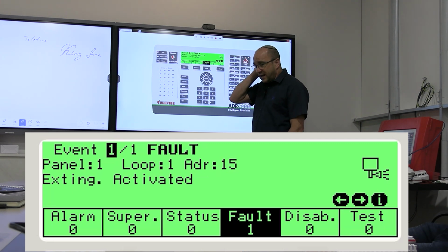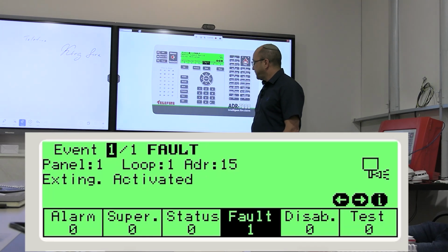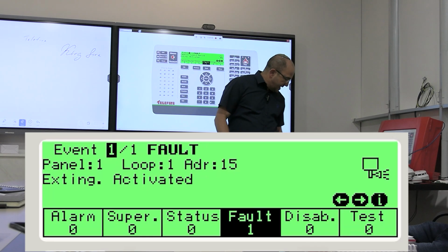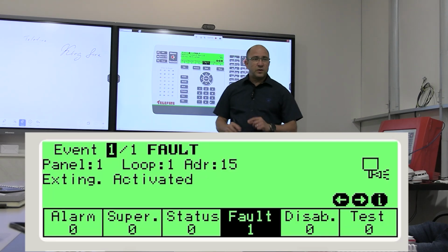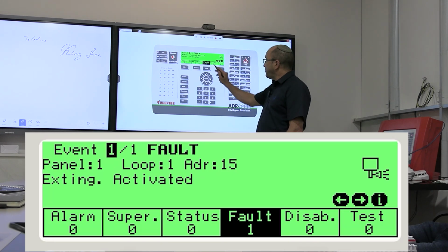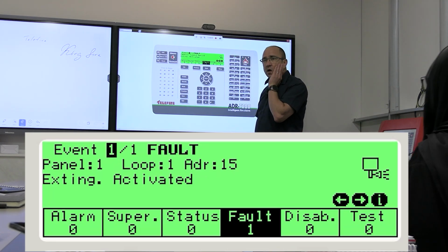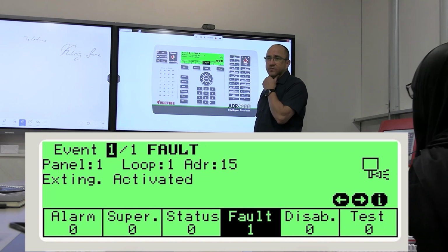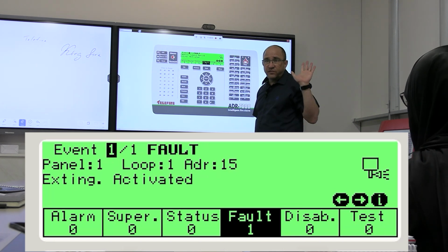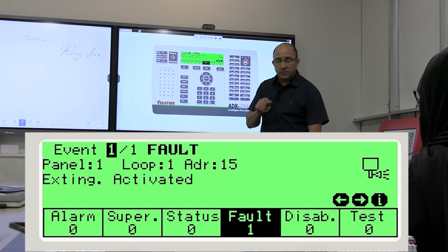Okay, now I have hearing problems. Silence, buzzer. Very good. Now, what's written? What's the fault that I have? I have one fault. What is the fault? The address is number 15. Very good. What is the fault? Extinguisher activated. That's the fault. Extinguisher activated. What do I do to get rid of it? Let's do reset.